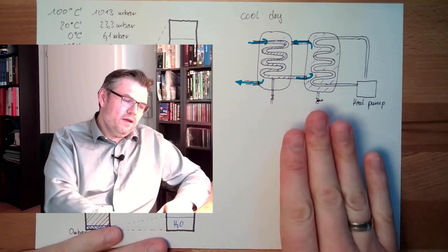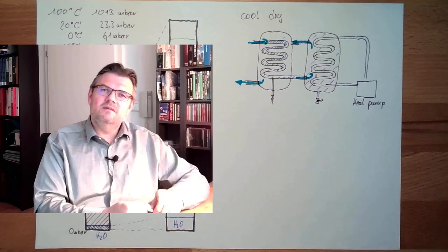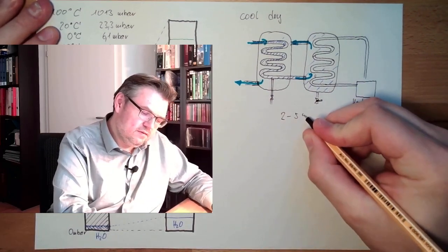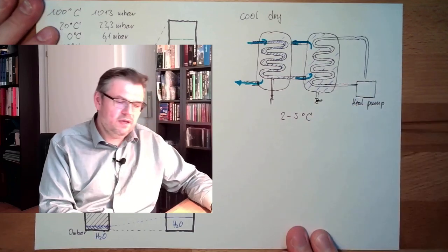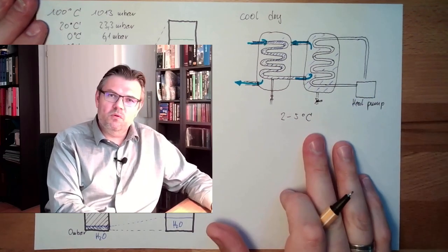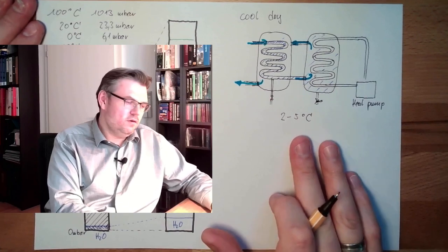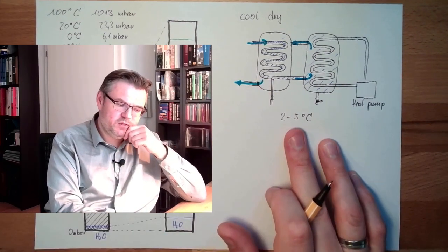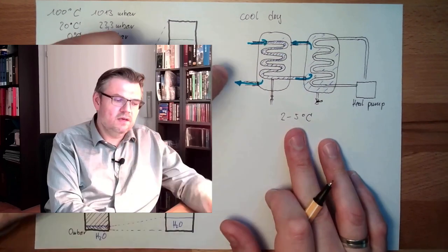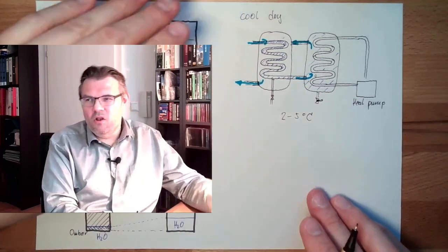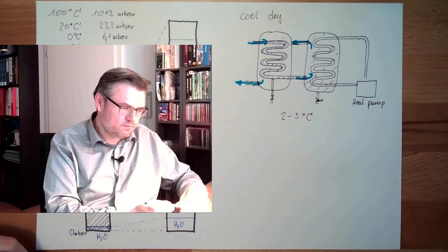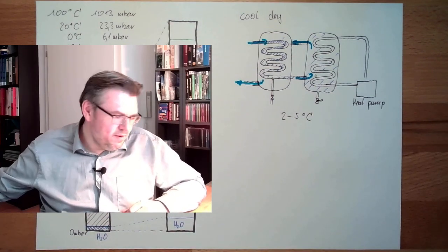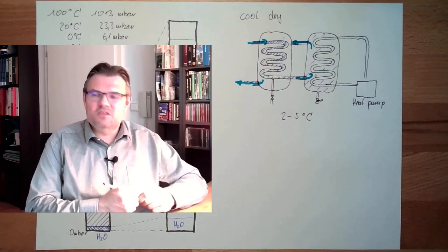However, you can reach pressure dew points at only around 2 to 5 degrees Celsius. This would be the Drucktaupunkt, the pressure condensation temperature, 2 to 5 degrees. So it's not that low. Then there's also a possibility which is called adsorption.